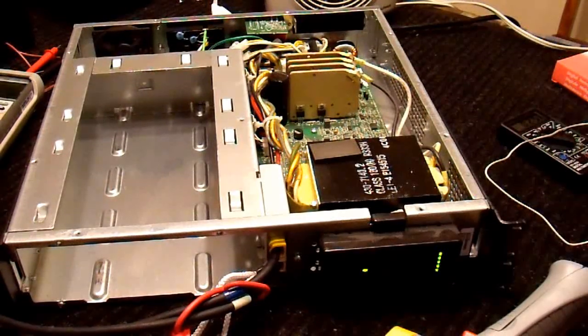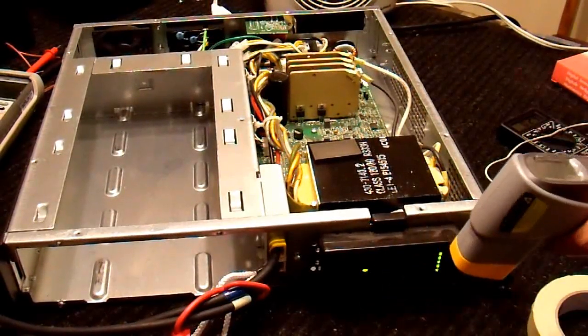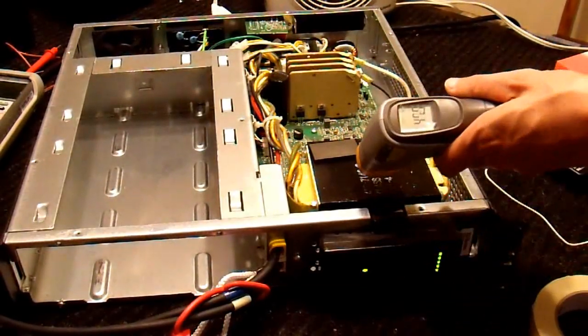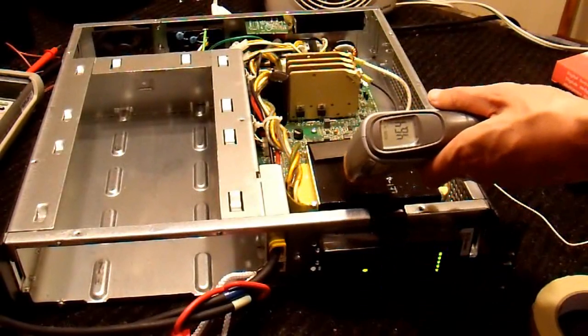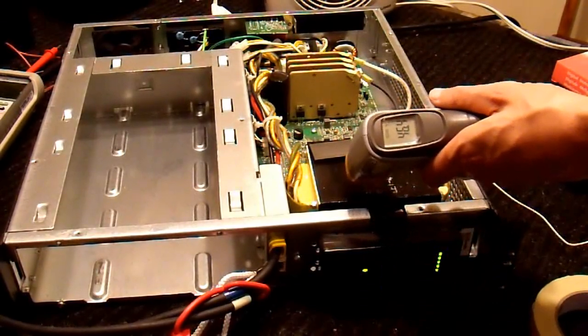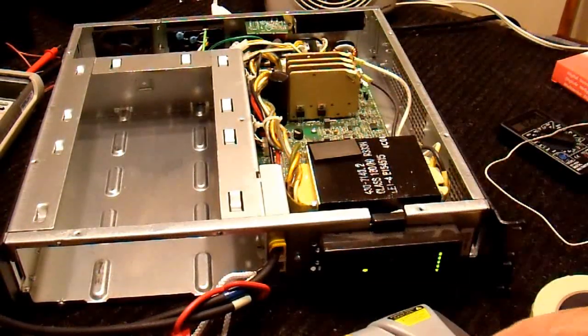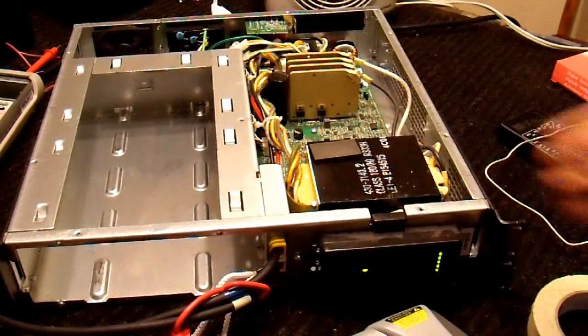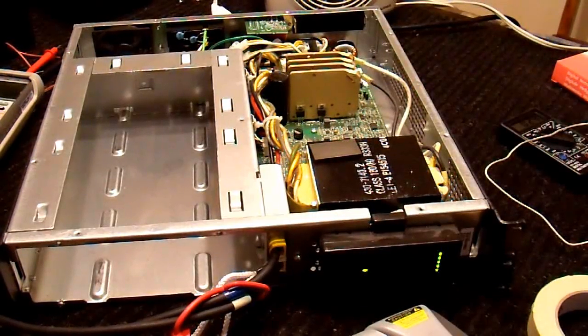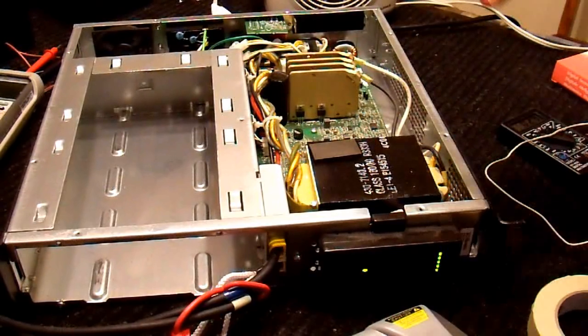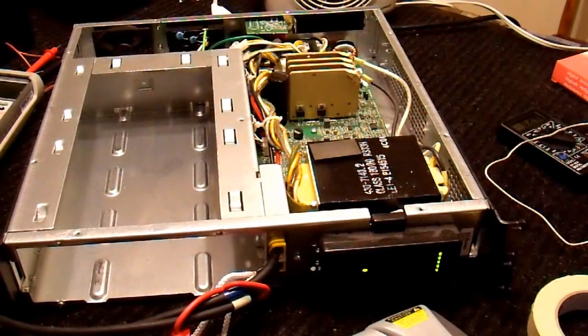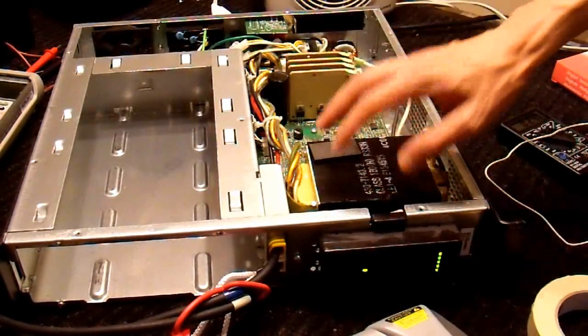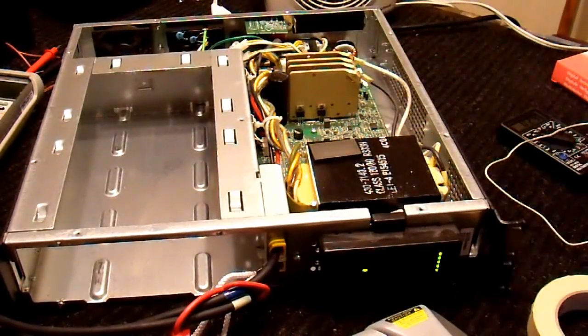That's the 50 watts of loss I mentioned earlier, and it's raised the temperature from about 25 degrees Celsius in here to, we'll say 50 once it's stabilized. So we've got a 25 C rise from 50 watts of load, which gives me an idea of how many watts of loss this transformer can take before we reach its 180 Celsius limit.